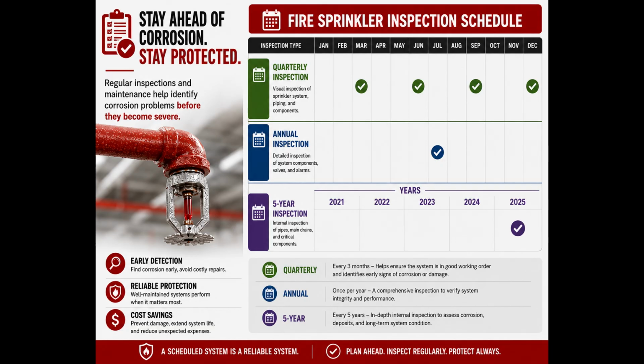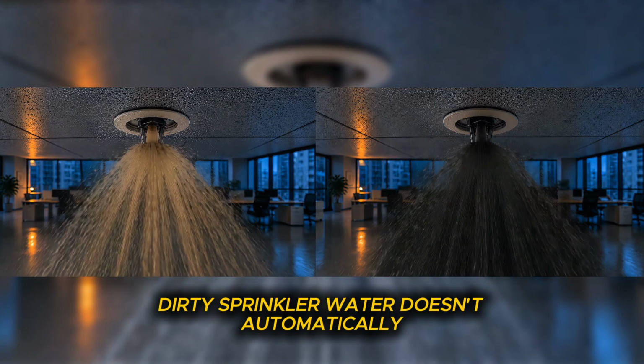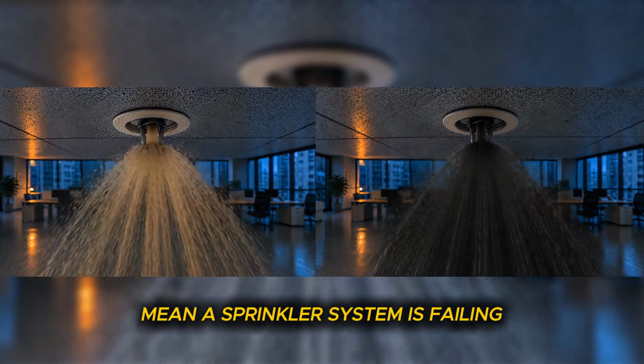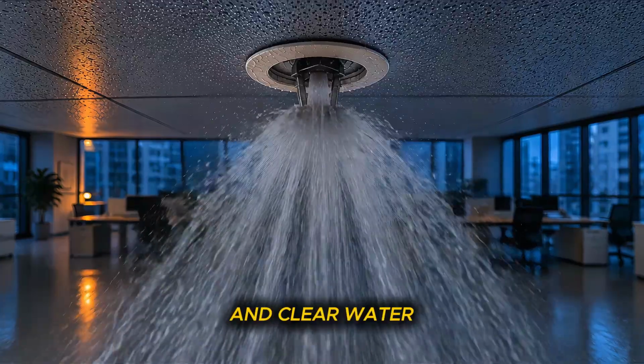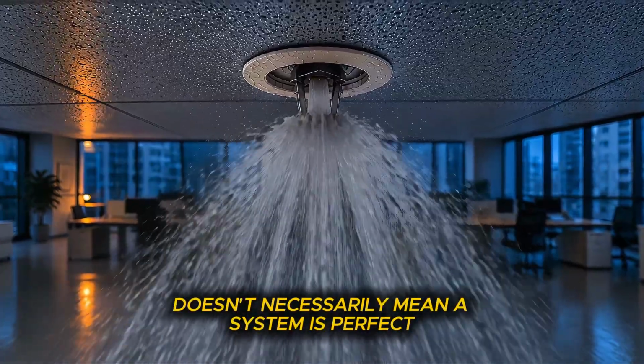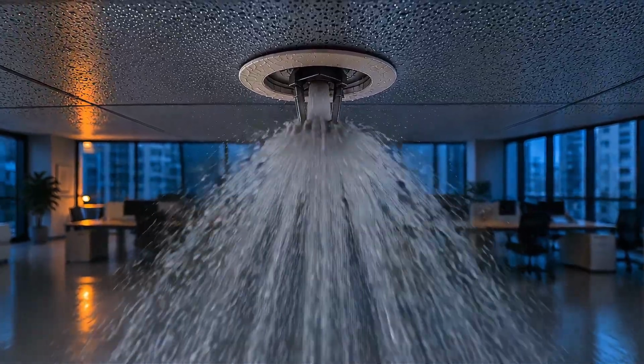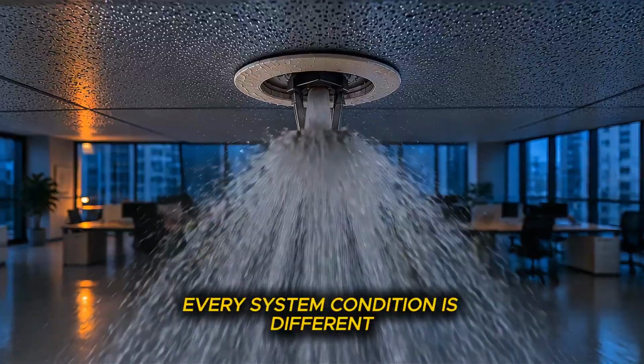Quarterly, annual, and 5-year inspections all play an important role in keeping a sprinkler system reliable. The 5-year inspection is especially important for catching internal corrosion, buildup, or hidden pipe issues that can lead to dirty brown or black water during system operation. Dirty sprinkler water doesn't automatically mean a sprinkler system is failing. And clear water doesn't necessarily mean a system is perfect. Every system condition is different.